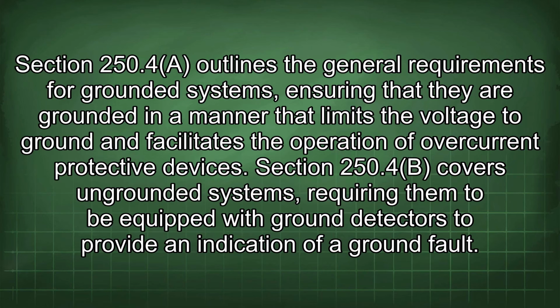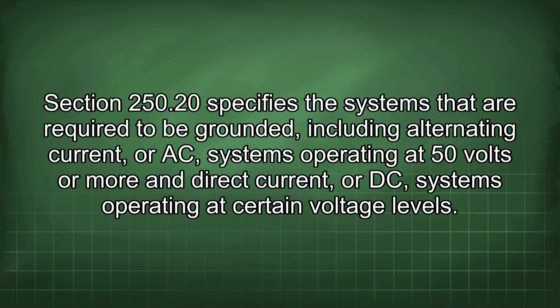Section 250.4(B) covers ungrounded systems, requiring them to be equipped with ground detectors to provide an indication of a ground fault. Section 250.20 specifies the systems that are required to be grounded, including alternating current, or AC, systems operating at 50 volts or more, and direct current, or DC, systems operating at certain voltage levels.